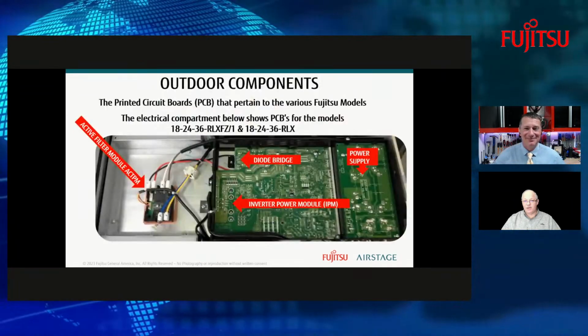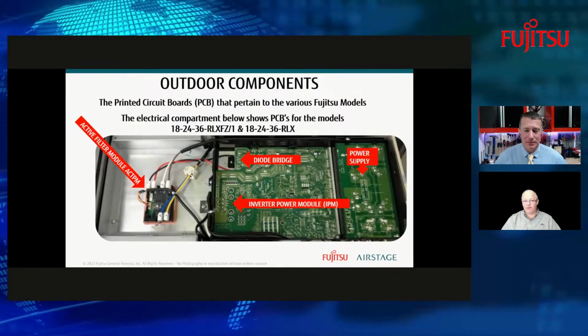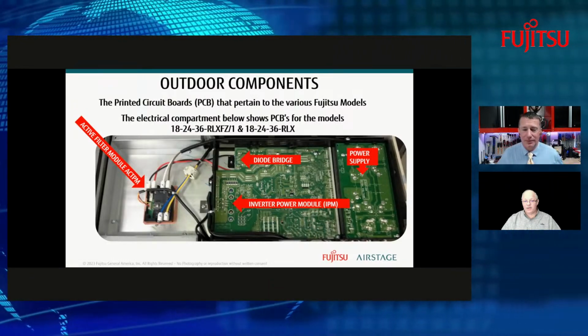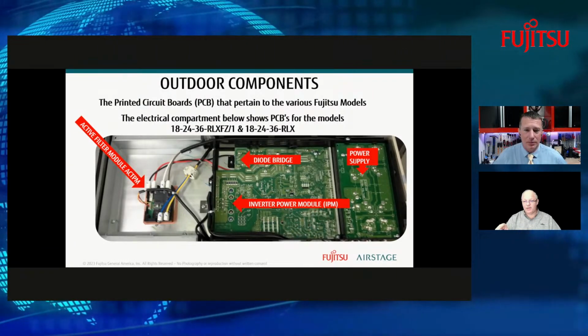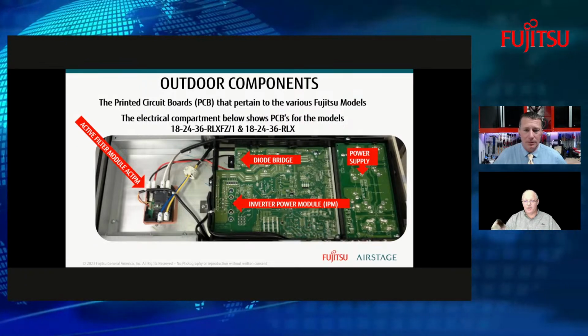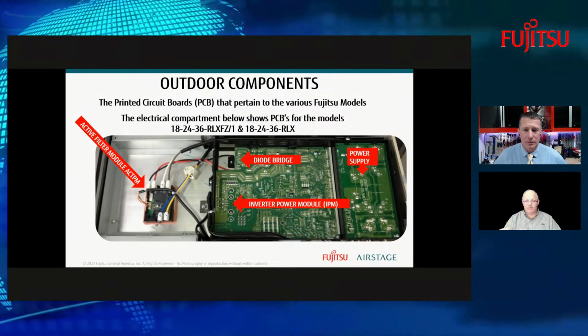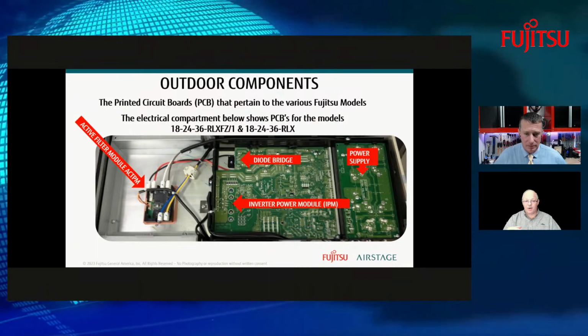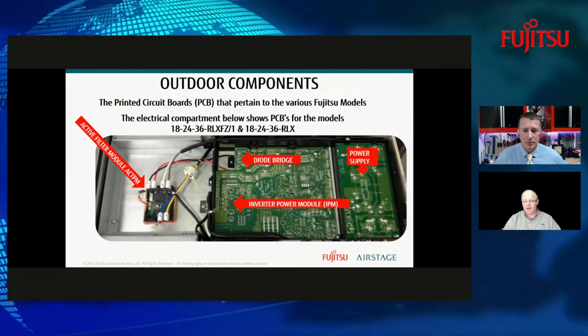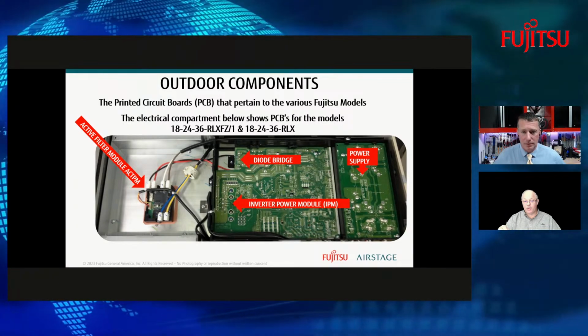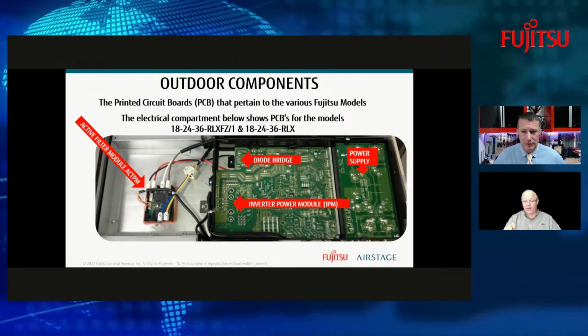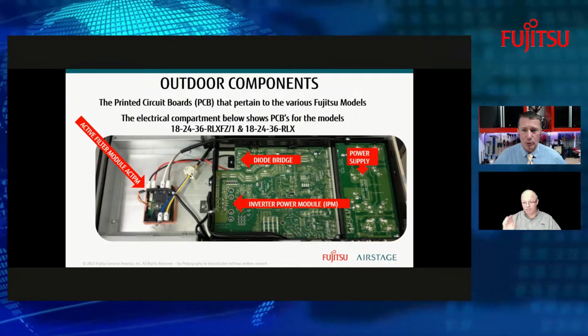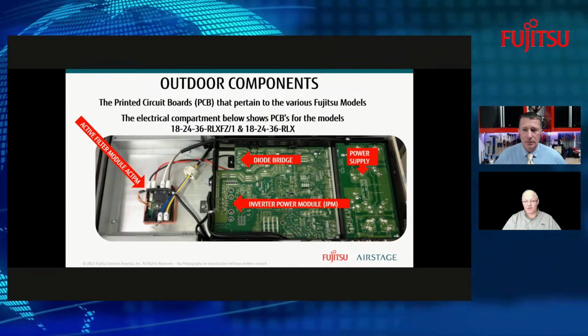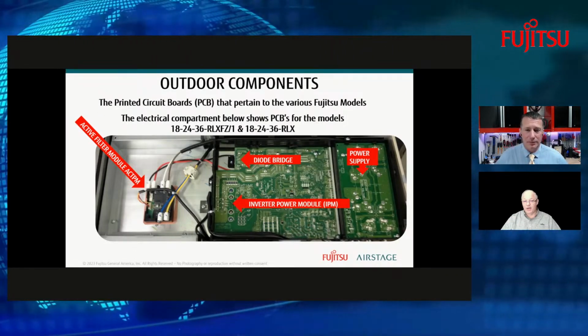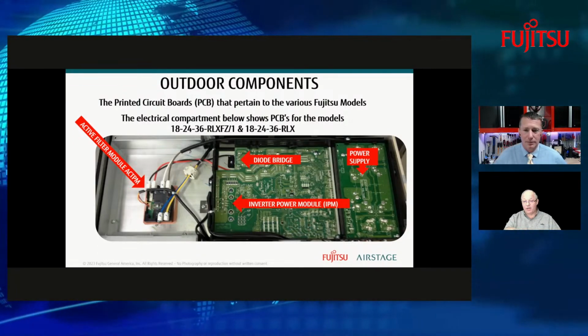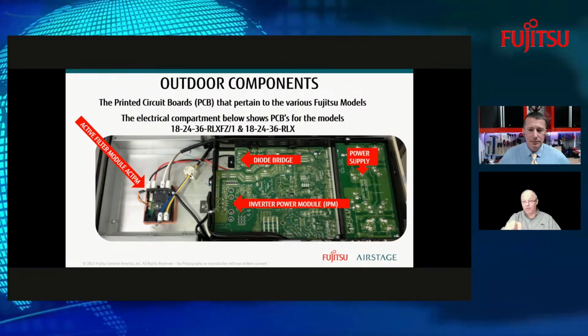Very nice. All right. So if you take the top off the equipment, this is just a nice little picture that shows where the power supply is on the right. You can see that you've got your diode bridge. The diode bridge then feeds over to the active filter module. The active filter module sends information back over to the inverter power module, which is, you can see the arrows pointing to the area. That's the piece of the board that takes care of the speed of the compressor and how it's going to modulate.